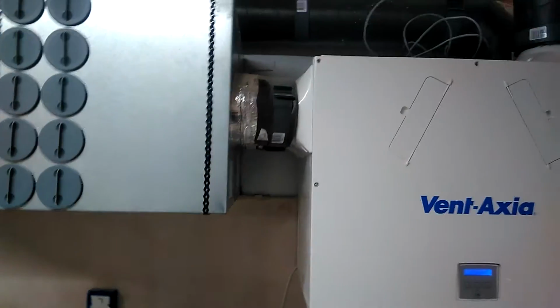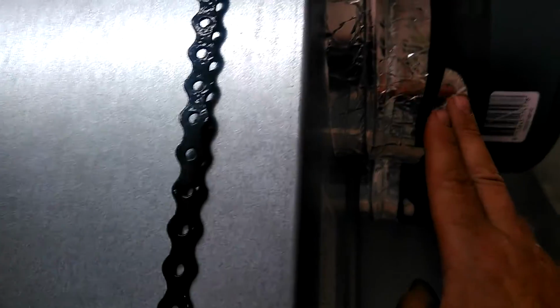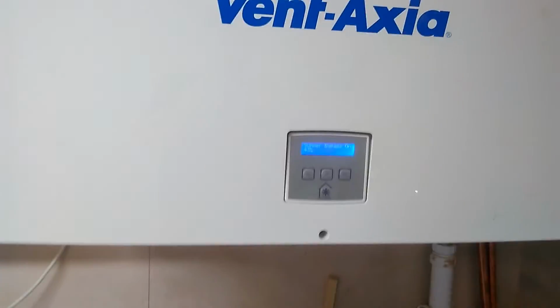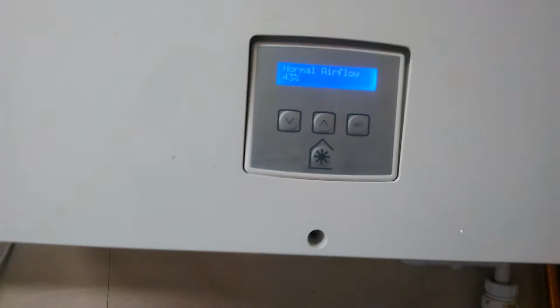We balanced the machine by inserting a probe into the ducts here, like I explained at first fix. This little piece of tape is covering a tiny little slot where I inserted the Testo probe anemometer, and there's one on the extract side as well. So we've plugged up the holes, and that's nice and balanced. So let's just move to the controls and we'll have a brief chat about what goes on there.